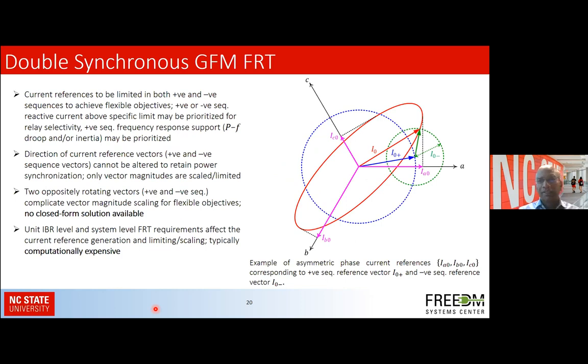So I'm not going into the details, but when we break it up into positive and negative sequence, the positive sequence limits are shown by this blue circle. It has to have a larger component because it has to support the real power component as well. The negative sequence is smaller, and the net current trajectory is the combination of the two, which takes this elliptical form. So from the inverter capacity limit, this constraint has to be maintained, that the absolute maximum limits of the inverter are within those elliptical characteristics shown here.